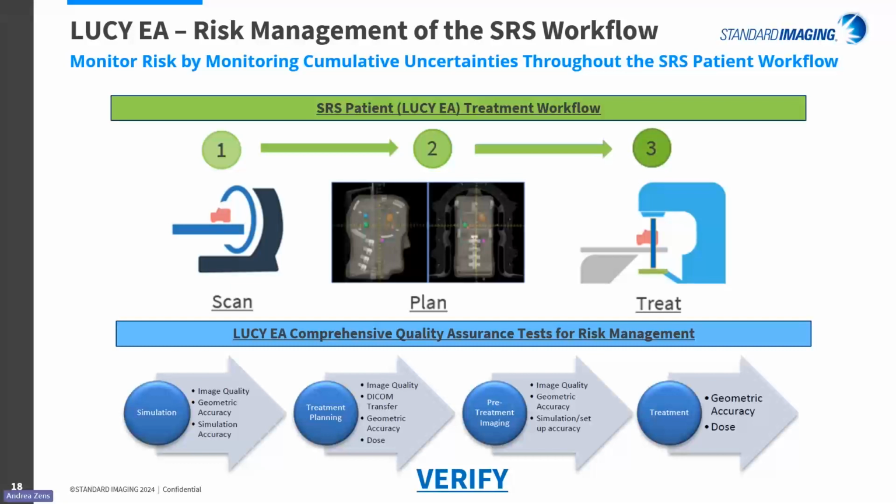daily and monthly radiation isocentricity test, Winston-Lutz test, using 1 or more of the 5 distinct targets, film plus ion chamber dosimetry with up to 6 distinct targets, plus an irregular avoidance structure in the mix. Accomplishing so much with so few inserts, swappable in an open mask system, makes Lucy EA ideal for standardization across sites and machines.